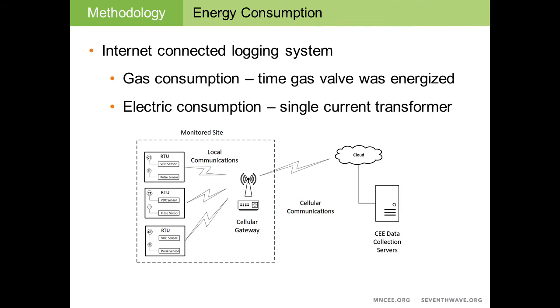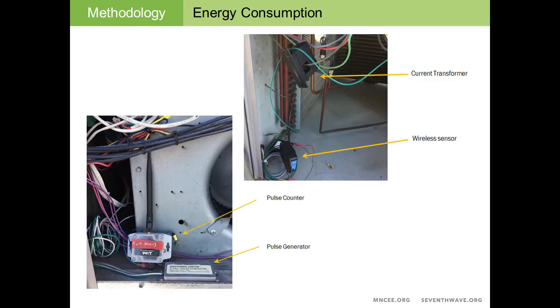So we were able to get data pretty accurately and pretty quickly to understand how the consumption of the units was working, and really to check on our monitoring system. Here's an example: there are 2 pictures of the monitoring equipment. The lower left shows the pulse counter with the red tape on it, and then the pulse generator, which is hooked in parallel to the gas valve, which gives us a pulse rate whenever the gas valve is active. The upper right-hand corner shows the current transformer on that brown wire, and then the wireless sensor that's measuring the 0 to 5 volt DC signal that's coming from that current transformer.